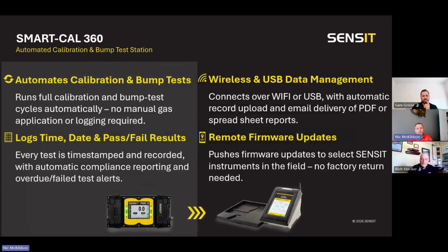For calibration, like Rich said, the PMD2 is fully compatible with our current SmartCal 360 station. A lot of our customers that have a SmartCal station today won't need a separate calibration station for the unit. The only additional gas required would be 1,000 parts per million methane. There's already a port assigned on the station, so there's no reprogramming involved - just get that additional gas, hook it up to that port, and you'll be able to calibrate the instrument right on the cal station.